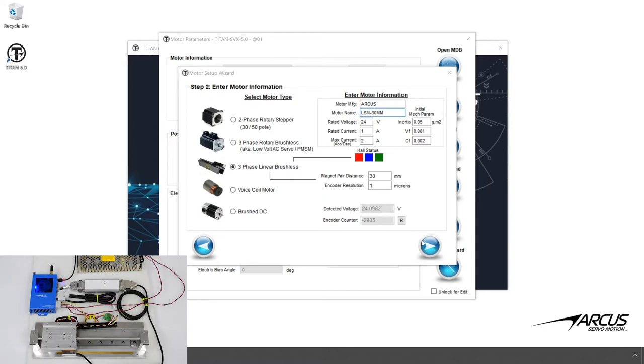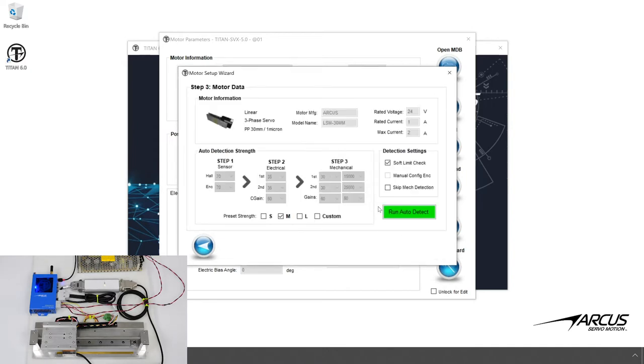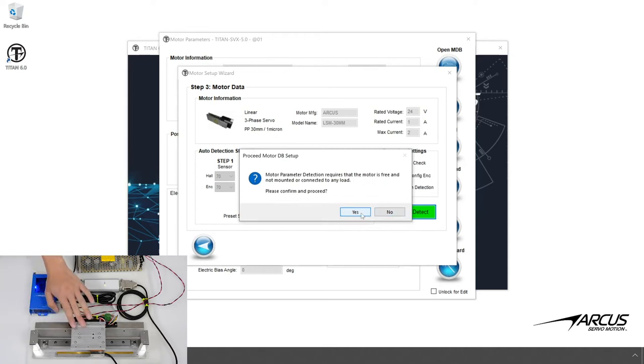Next, we will perform the auto detect routine. Make sure the motor doesn't have any load and is on a stable surface. Let's move the motor stage to the middle, as the first test involves moving the motor to find the encoder direction. First, the Titan will check for the encoder direction.